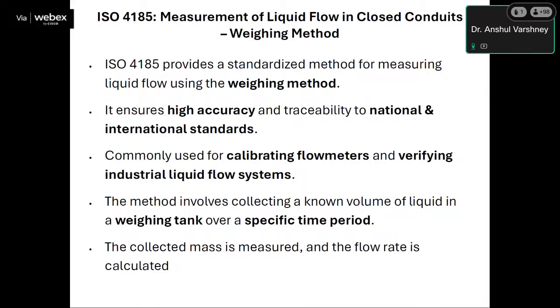For flow meter calibration, the primary method we use is the weighing method, or gravimetric method. That is a primary method because it is directly related to SI units, mass and time. ISO 4185 provides the method and other details for measurement of liquid flow in closed conduits using the weighing method. It provides a standardized method for measuring liquid flow using the weighing method. It ensures high accuracy and traceability to national and international standards. It is commonly used for calibrating flow meters and verifying industrial flow systems.